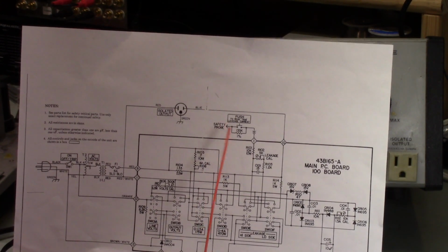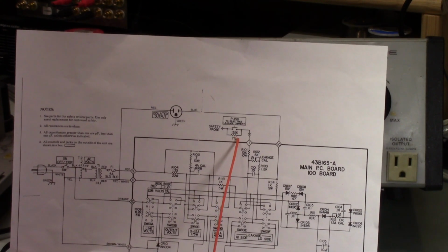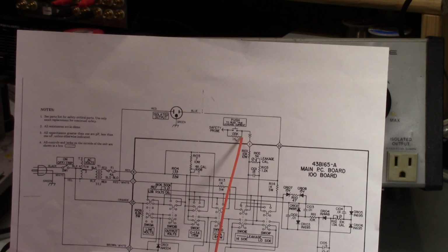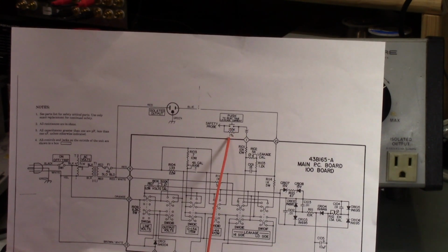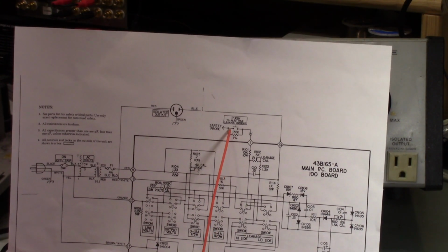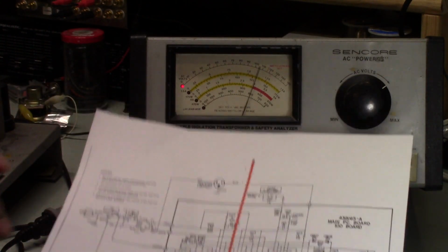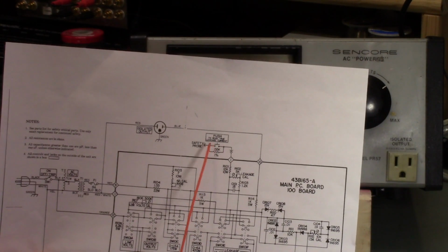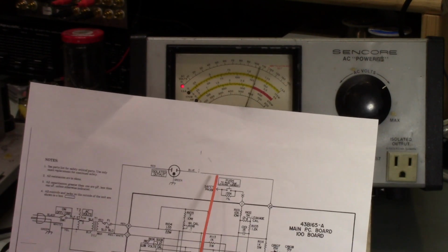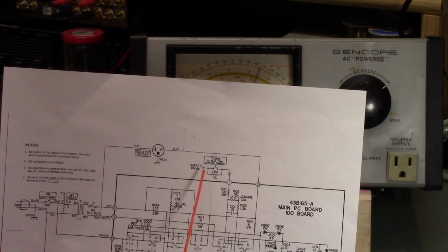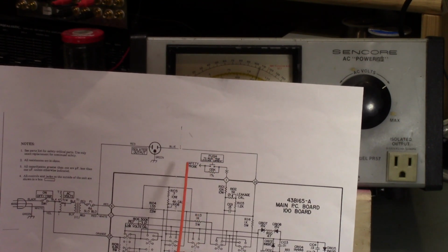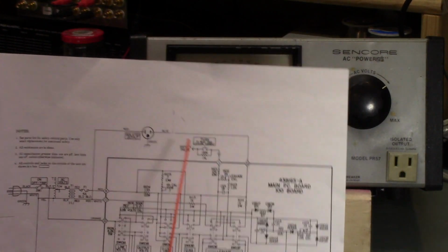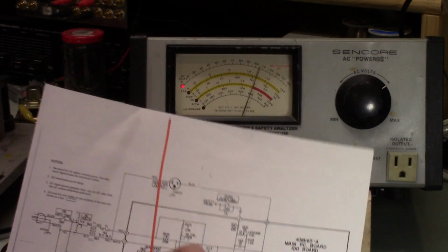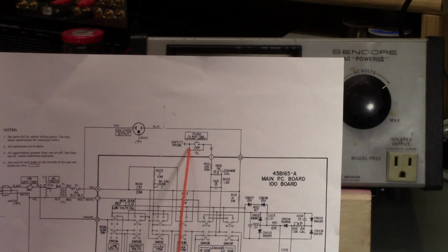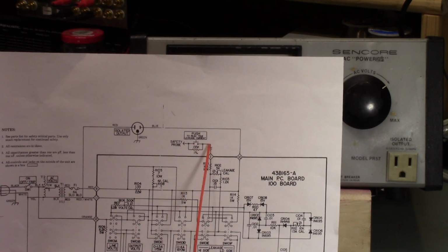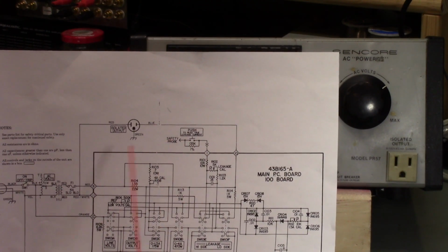The reason this resistor is there is it allows you to check for high levels of AC voltage, up to 120, and protects your meter from going full scale. It's not going to destroy the meter if this resistor weren't there; it just makes it easier to use, as you'll see. Having that little switch is helpful, and pressing it gives you a reading on your meter, if it's not already full scale, showing the actual current as seen by the safety probe.